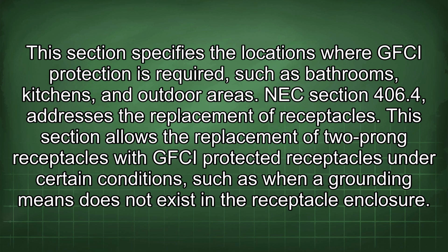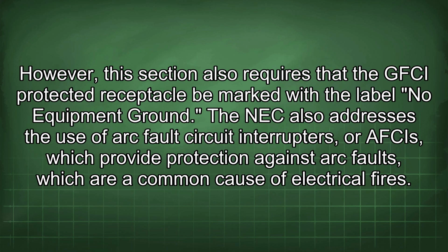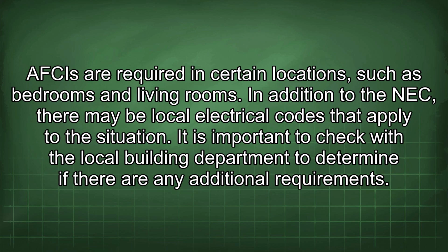NEC Section 406.4 addresses the replacement of receptacles. This section allows the replacement of two-prong receptacles with GFCI protected receptacles under certain conditions, such as when a grounding means does not exist in the receptacle enclosure. However, this section also requires that the GFCI protected receptacle be marked with the label "No Equipment Ground." The NEC also addresses the use of arc fault circuit interrupters, or AFCIs, which provide protection against arc faults, which are a common cause of electrical fires. AFCIs are required in certain locations, such as bedrooms and living rooms.